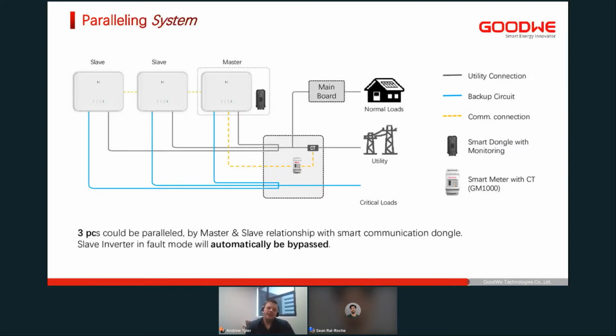Right, going into the key features of the new generation 2. Some of these have been improved, some are completely new to this generation. Firstly, parallel or paralleling of the system. What this allows you to do is to start off with 5 kilowatts, and if the customer would like to upgrade at a later stage, you can parallel a second 5 kilowatt to bring your total system size to 10 kilowatts. That would be 10 kilowatts on the backup circuits as well, not just on your grid connected loads.